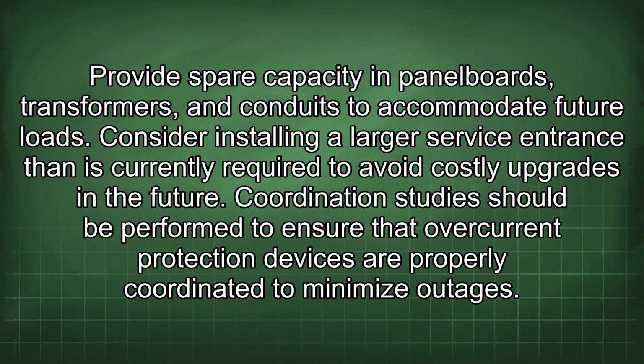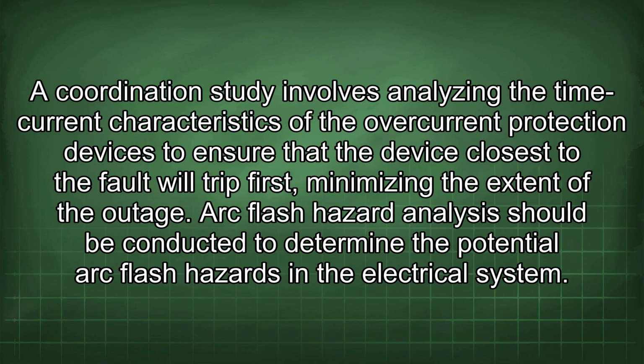Coordination studies should be performed to ensure that overcurrent protection devices are properly coordinated to minimize outages. A coordination study involves analyzing the time current characteristics of the overcurrent protection devices to ensure that the device closest to the fault will trip first, minimizing the extent of the outage.